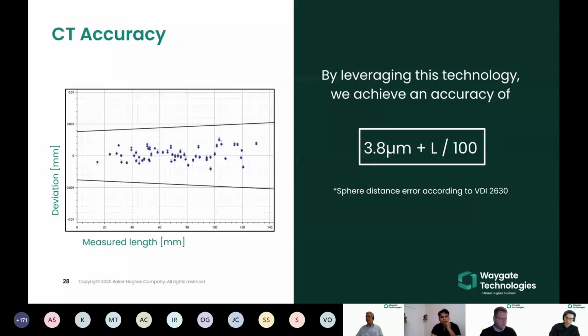And with all this technology that I've shown you in a very rough overview here, we are able to achieve an accuracy of 3.8 microns plus L, being the length you want to measure, divided by 100. And again, this is according to the VDI standard. So this is our specification for the V|tome|x M Metrology Edition 2.0. You can see here we did a lot of measurements between different spheres, the distances, and all these distances are within this 3.8 microns. So no deviation bigger than 3.8. Actually, it's a lot smaller than that. In this diagram here, it's around 2.5.